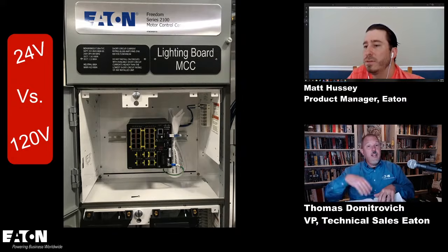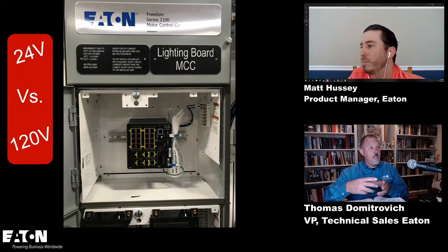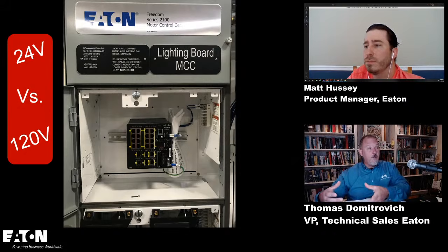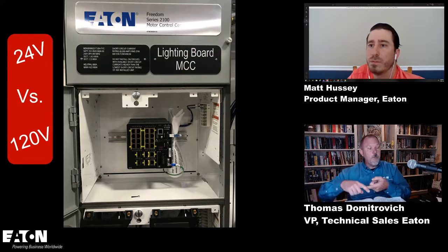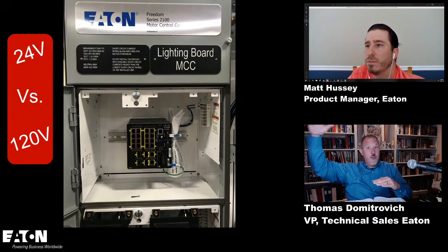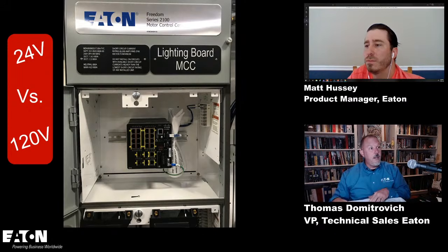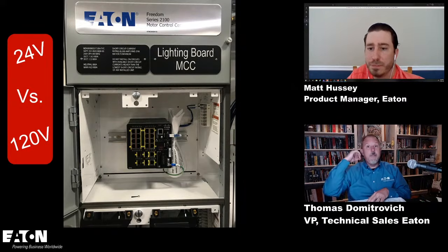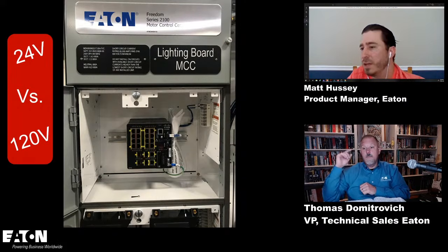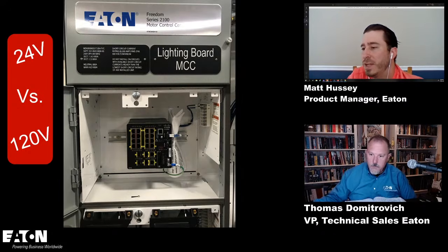So I may, in fact, be violating some of these distance requirements, but I'm testing it as part of the UL standard together. As long as I'm a listed product and tested that way, I can get away with doing certain things because I'm going to the nth degree and doing that evaluation in my factory. Right, that makes sense. But if somebody else installs it out in the field, that's a different story. That's exactly right. You'll have a lot of these applications where drives and controllers are all co-located in the panels.